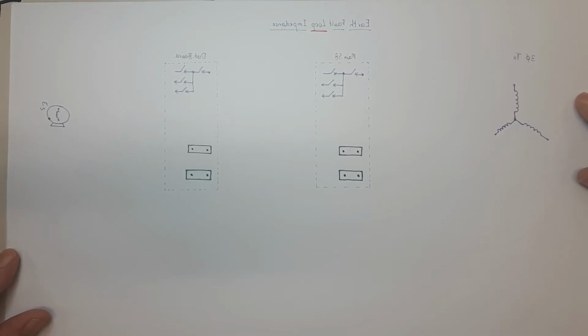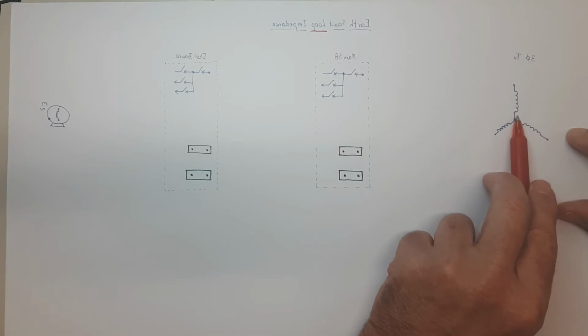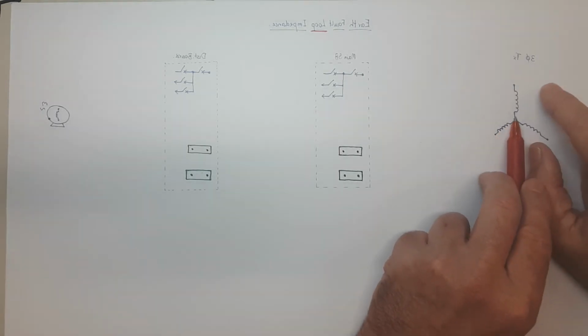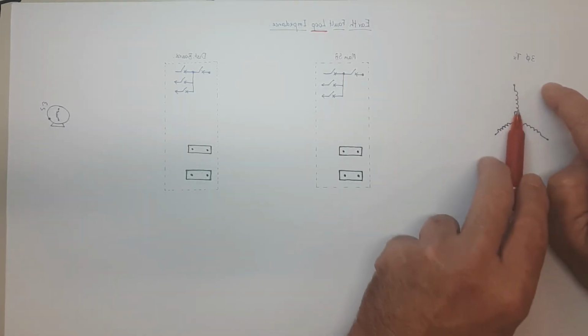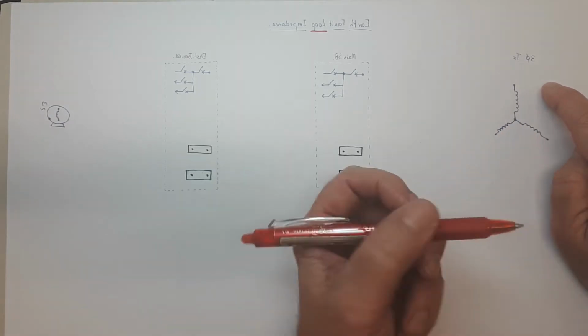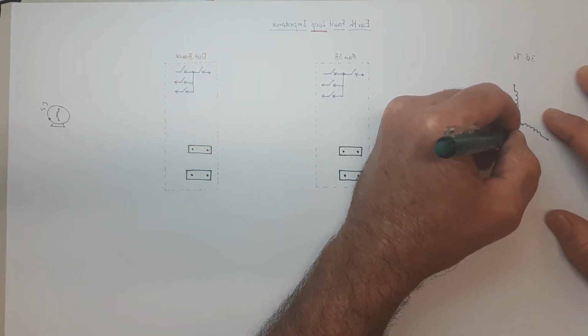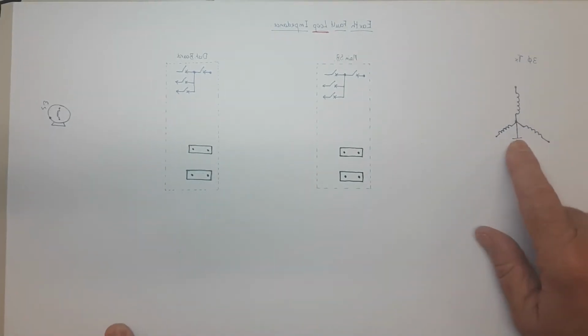That's what table 8.1 is all about. There are maximum values for different circuits and different circuit breaker sizes. So let's just start with the transformer here. The first thing in our loop is our phase winding. There are three on here. And of course, as you know, at a transformer, the windings will all be connected in star, and the star point is earthed. So that's the first point that's earthed.